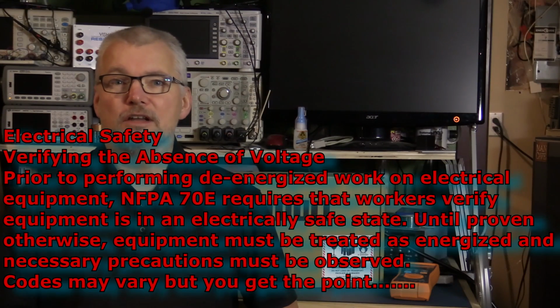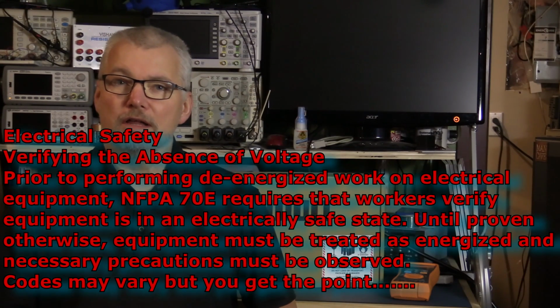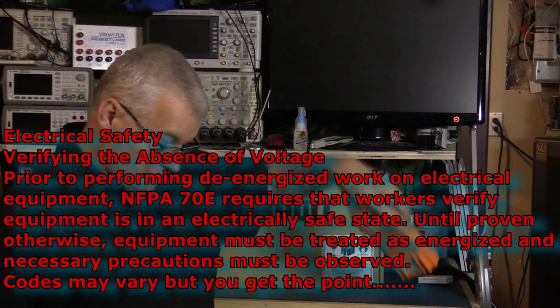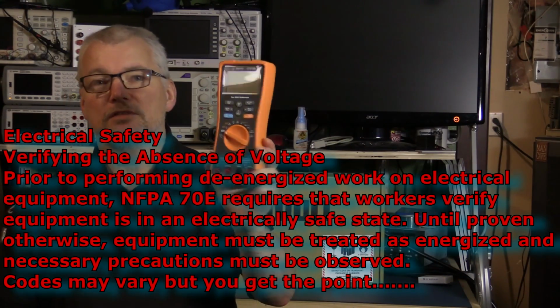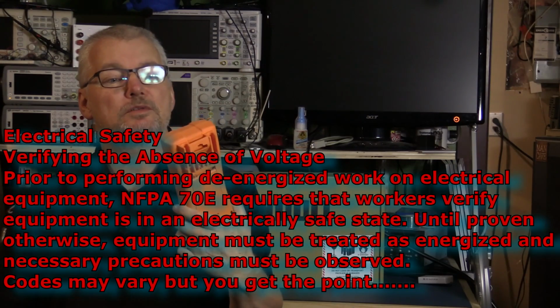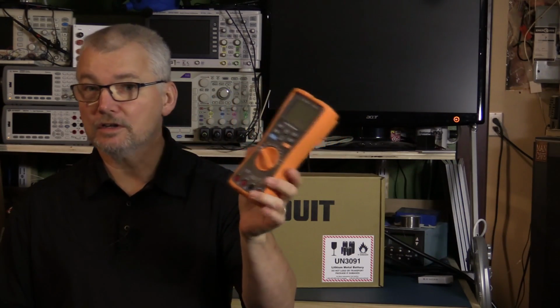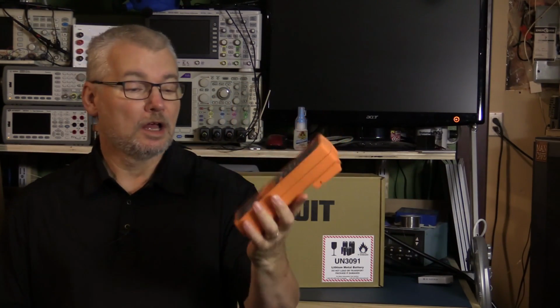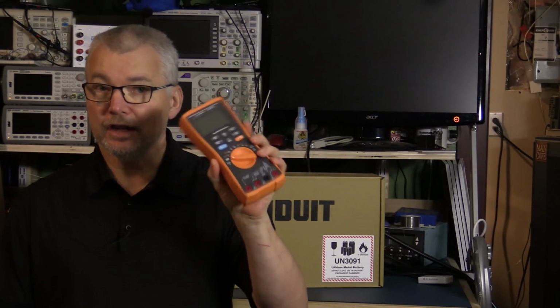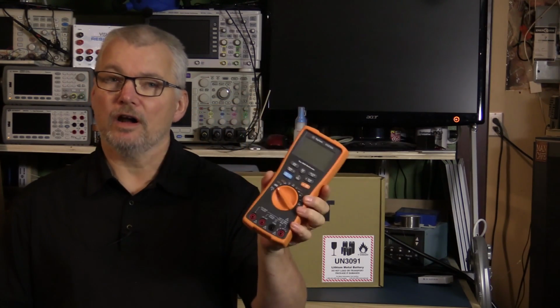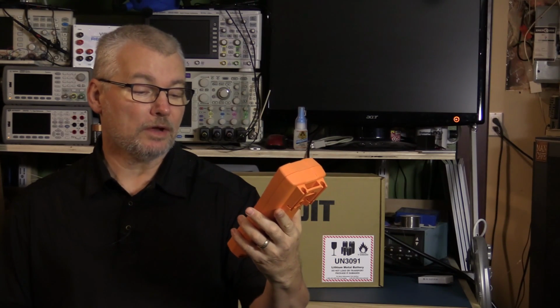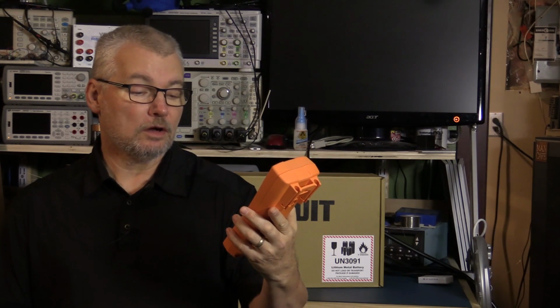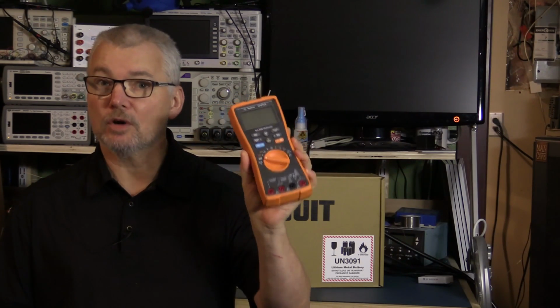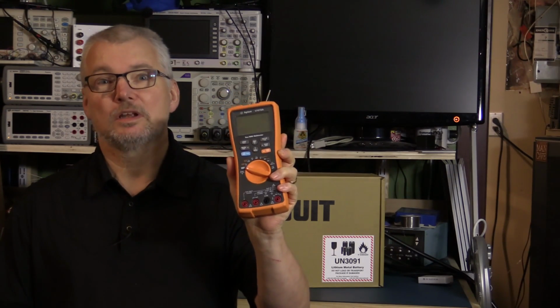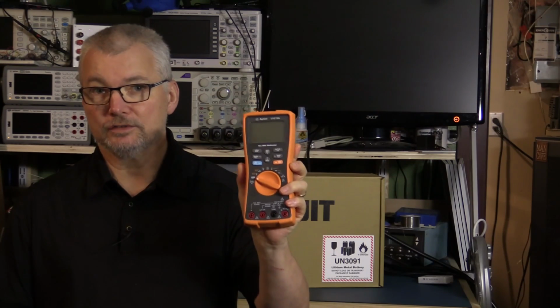Part of that process involves getting a multimeter, something like this Agilent 1272A or equivalent, could be a Fluke or somebody else's, that's got a suitable cat rating for the environment you're using it in. This one is rated up to cat 3, so it can go up to about 1,000 volts with the appropriate probes on. Not all probes work to cat 4 or cat 3.